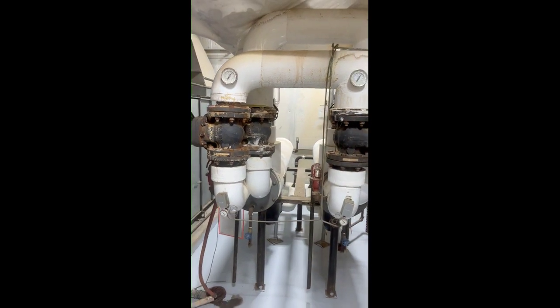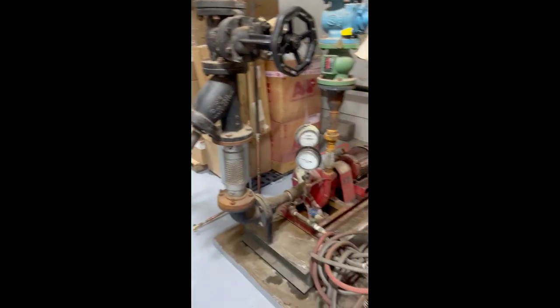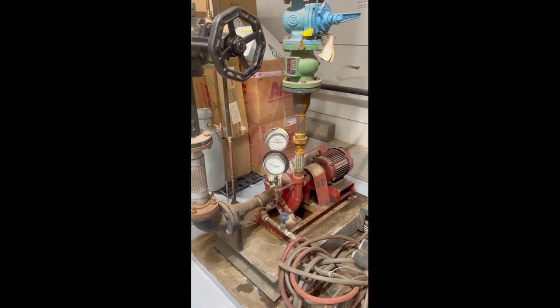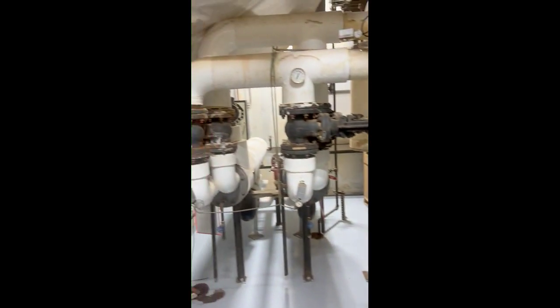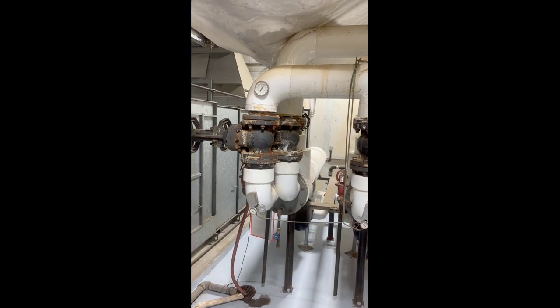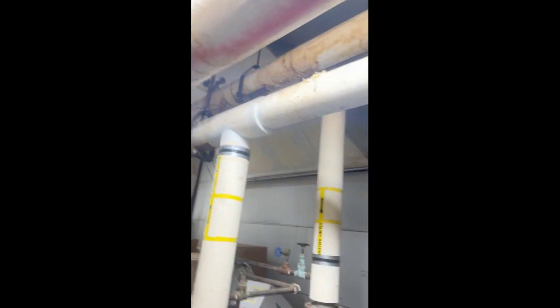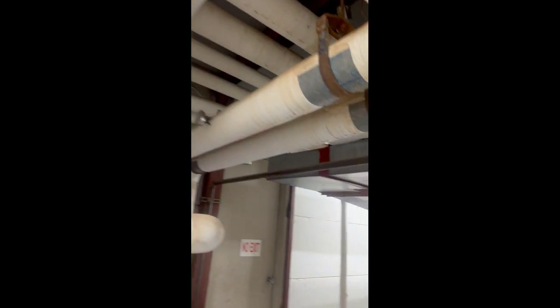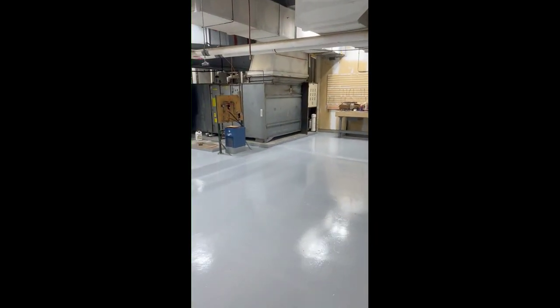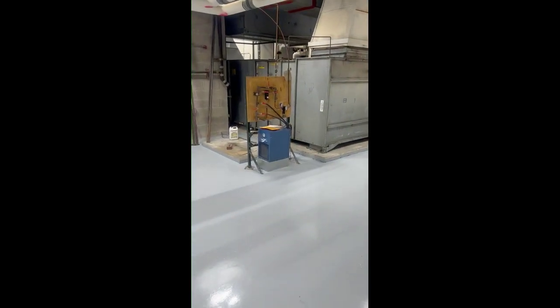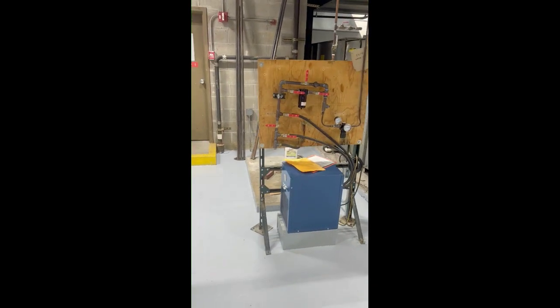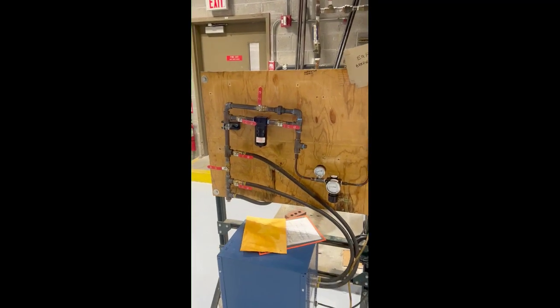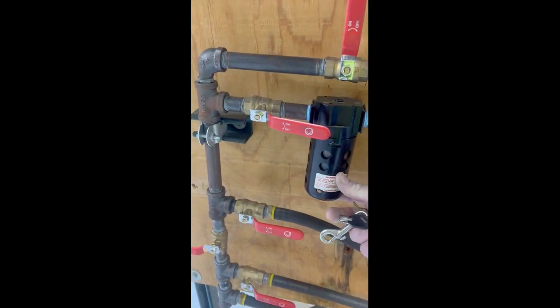These are hot water heat exchangers, and they take regular fluid hydronic hot water that heats our registers and our reheats in the building, and it gets heat introduced by virtue of steam. So that steam goes all the way from where we just were, all the way back to that steam unit. So that looks okay. Got my air dryer, my water separators for my air. Looks good there.